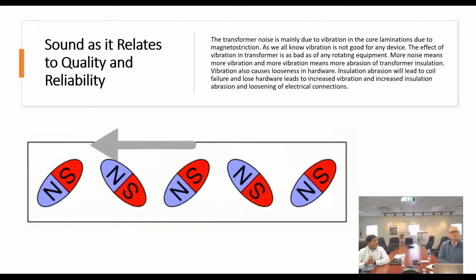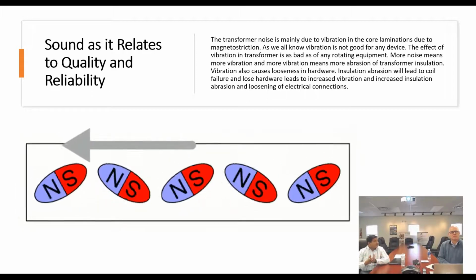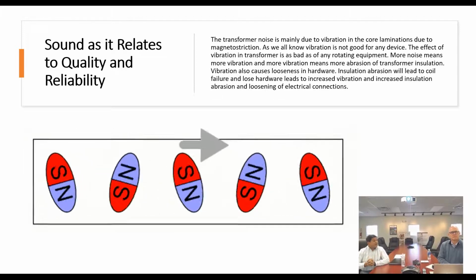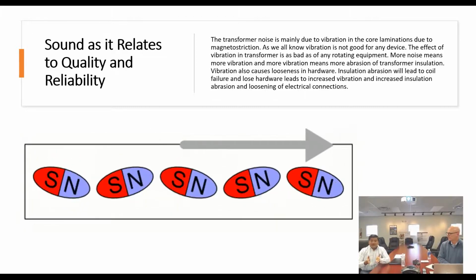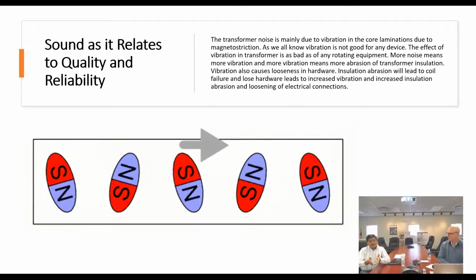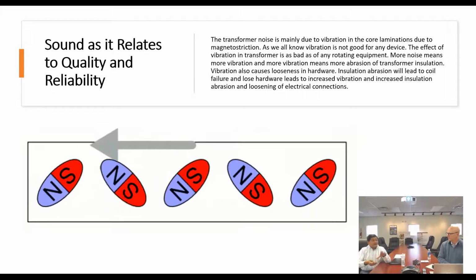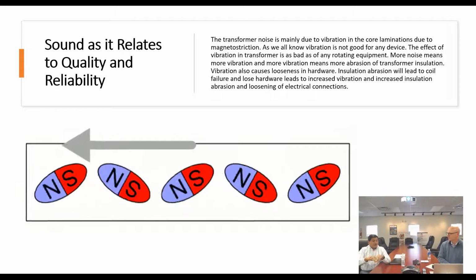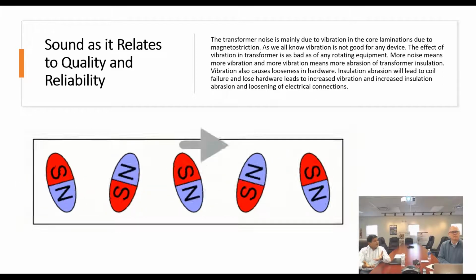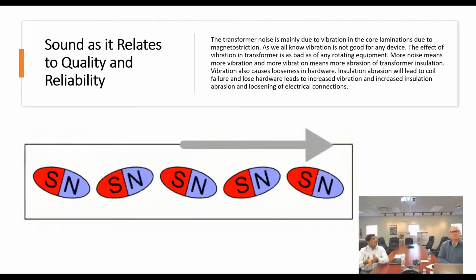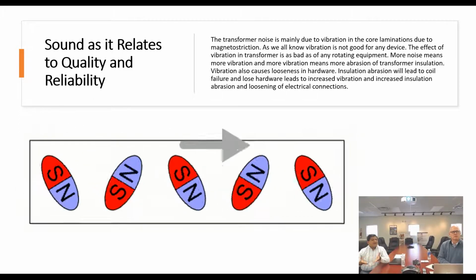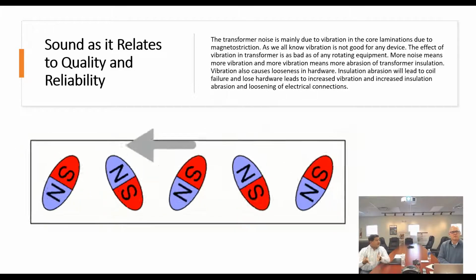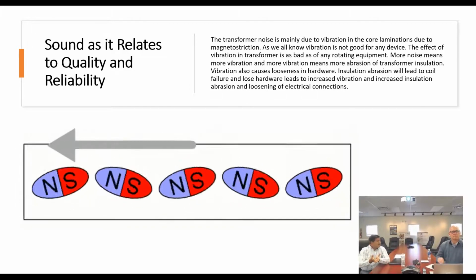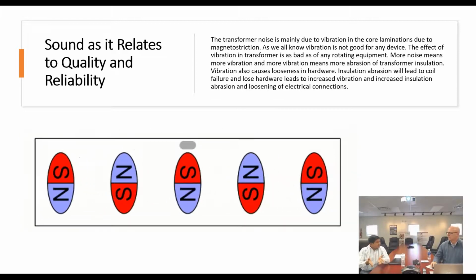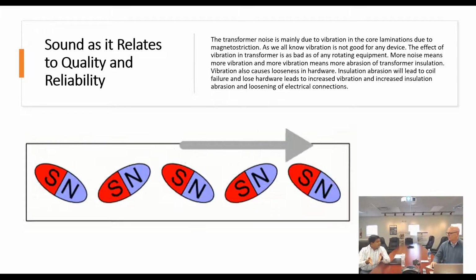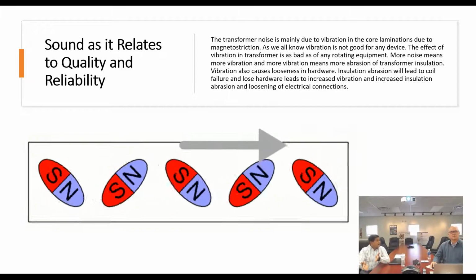As the winding insulation reduces, that increases the gap between the windings, so the pressure on the winding is reduced, and that makes the hardware of the clamping structure loose. That means eventually there will be more vibration. So we have reduced insulation, our coils are loose, the hardware is vibrating more, and eventually that will lead to failure of the core and coil assembly. This is similar to any vibrating or rotating element that we see in our life. Take a car, the same thing. If there is more vibration, you have loose hardware, and eventually it leads to failure over a period of time.